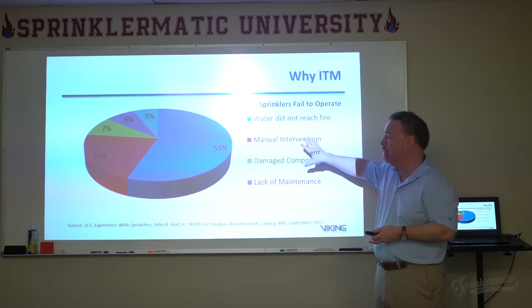So the standard NFPA 25, why 25? Well, 25 is actually a conglomeration of a lot of standards that, up until 1992, had their own inspection, testing, and maintenance guidelines. NFPA 13 had a document called NFPA 13A, NFPA 14 had NFPA 14A, and other installation standards for fire pumps, underground piping, and so on had chapters on inspection, testing, and maintenance. But it wasn't until 1992 that all of those items were pulled out of the installation standards and put into their own document, NFPA 25, which handles all of them.